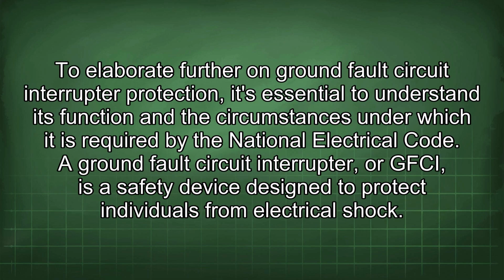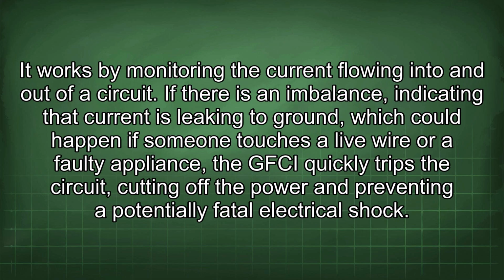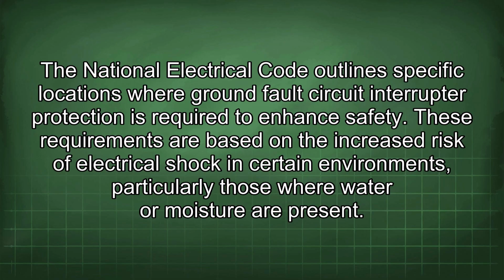code. To elaborate further on ground fault circuit interrupter protection, it's essential to understand its function and the circumstances under which it is required by the National Electrical Code. A ground fault circuit interrupter, or GFCI, is a safety device designed to protect individuals from electrical shock. It works by monitoring the current flowing into and out of a circuit. If there is an imbalance, indicating that current is leaking to ground, which could happen if someone touches a live wire or a faulty appliance, the GFCI quickly trips the circuit, cutting off the power and preventing a potentially fatal electrical shock. The National Electrical Code outlines specific locations where ground fault circuit interrupter protection is required to enhance safety.